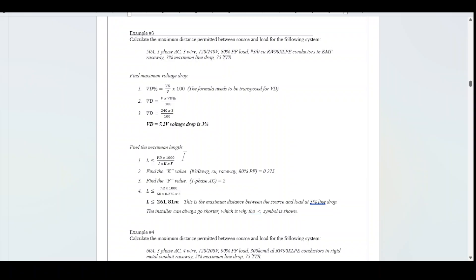Now find the maximum length using the L equation: L equals V_D times 1000, divided by K times F times I. The K and F values are determined from the circuit properties. Plugging in all values gives 261.81 meters — the maximum distance between source and load at 3% line drop. One could always go shorter, which is why the less-than-or-equal symbol is shown.